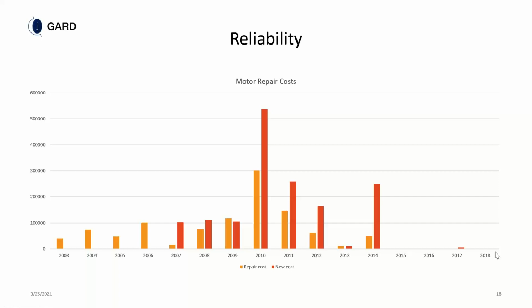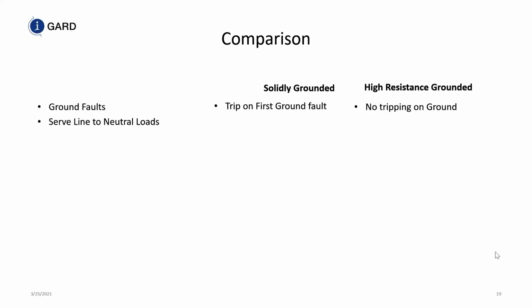But their motor repair costs reduced greatly, because when you have a ground fault on a resistance grounded system, the damage at the point of fault is so greatly reduced that you don't damage the equipment where the ground fault is. So in comparison, when you have a ground fault on a solidly grounded system, you must trip. On a resistance grounded system, you don't necessarily have to trip. Serve line to neutral loads? Yes, you can serve line to neutral loads on a solidly grounded system.